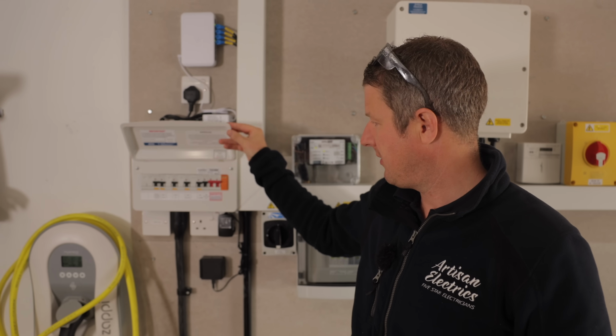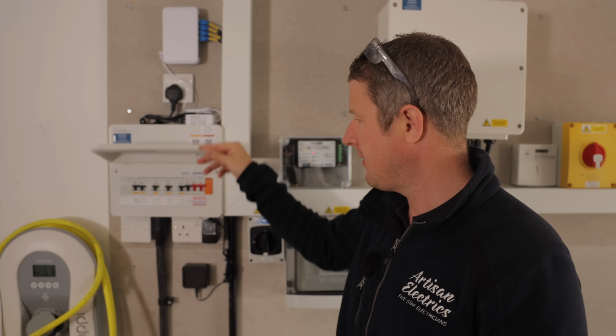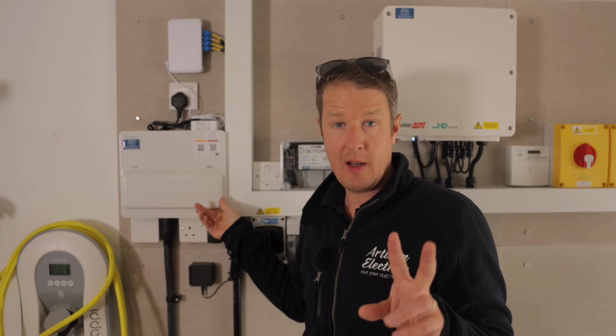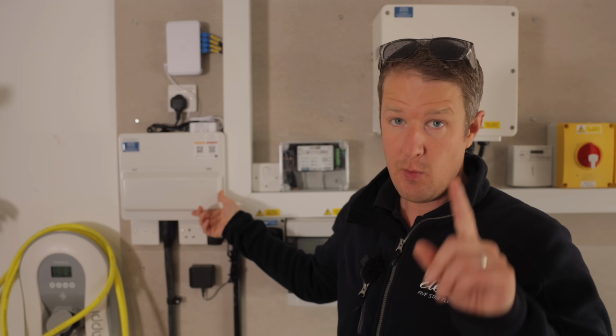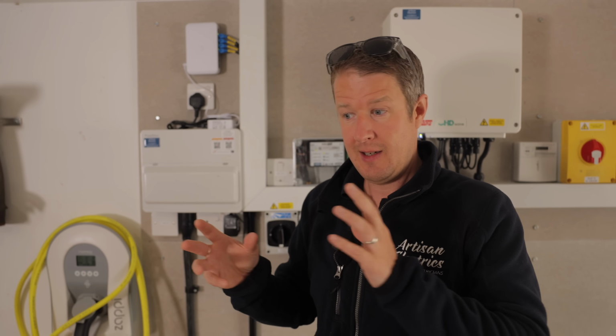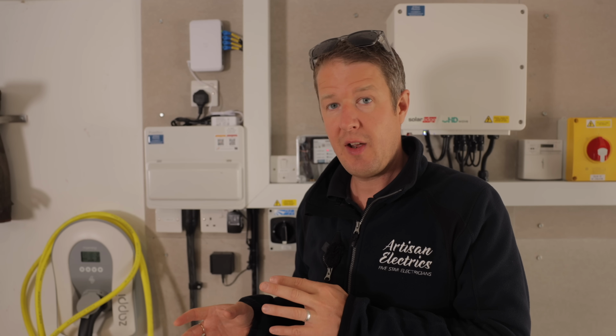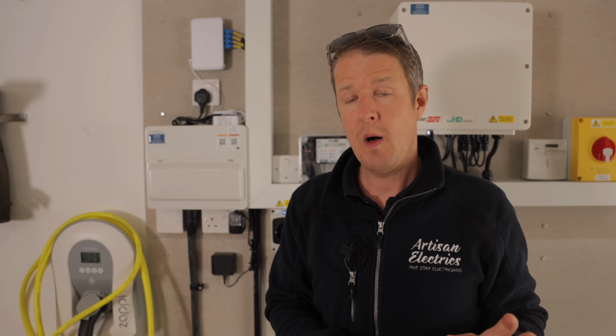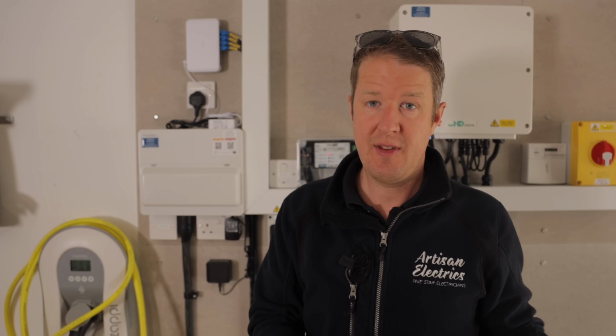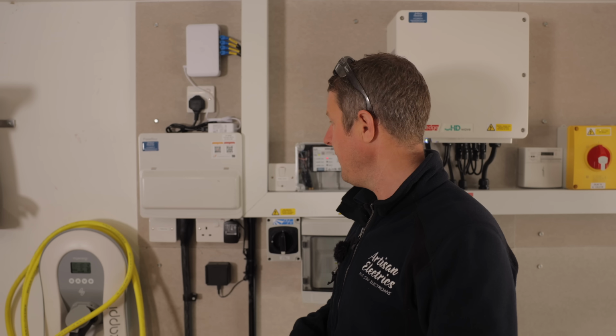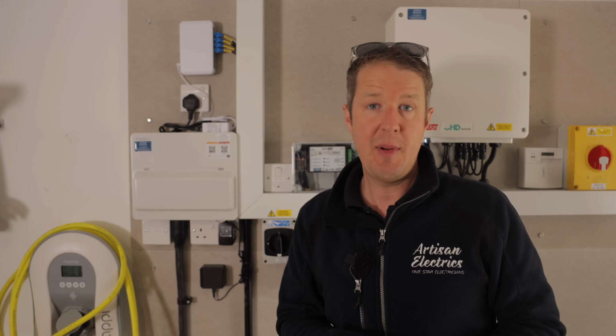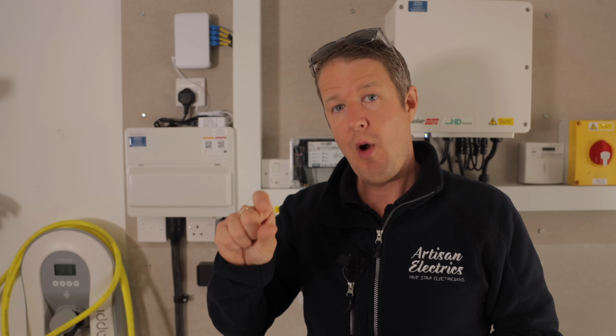So in this system we've got a consumer unit with various circuits. So we need 2 circuits for the Libbi system ideally. 1 circuit for the actual inverter. That is usually a 32 amp circuit breaker for a 5 kilowatt inverter, or a 16 or 20 amp breaker for the 3.68 kilowatt inverter. Then you need another circuit for the Libbi controller. That needs to be run off a 3 amp fused connection unit.